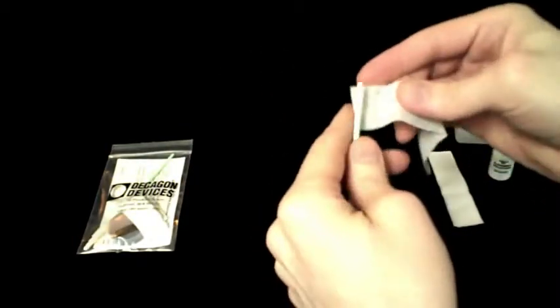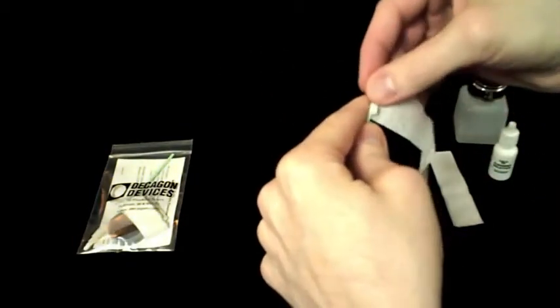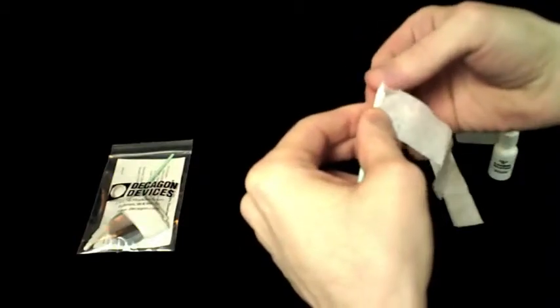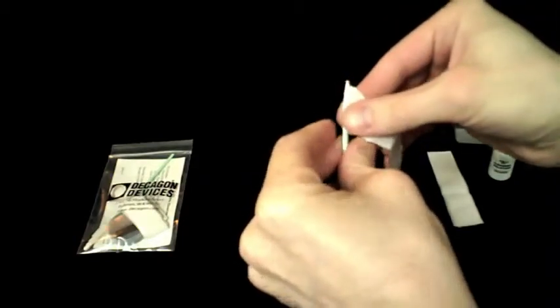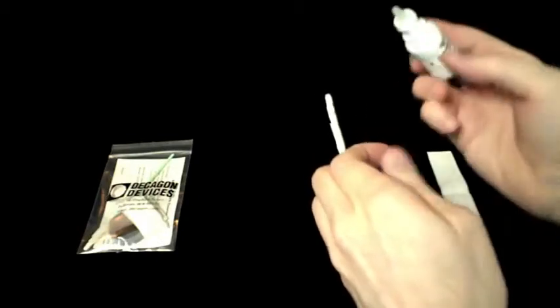Next, wrap a new kimwipe around the end of the thin plastic rod from the cleaning kit and moisten it with Decagon Cleaning Solution. Kimwipes are used for cleaning the Aqualab because they don't contain any adhesives or other additives that can get left behind during the cleaning process.